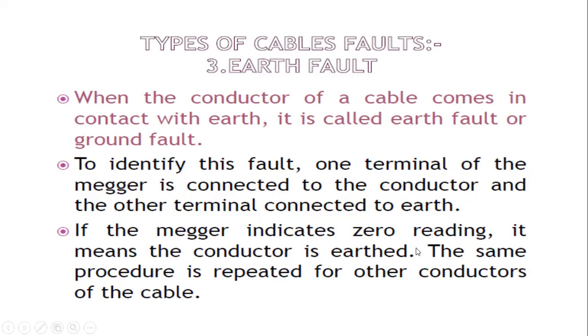If the Megger indicates a zero reading, it means the conductor is earthed. The same procedure is repeated for all other conductors of the cable.